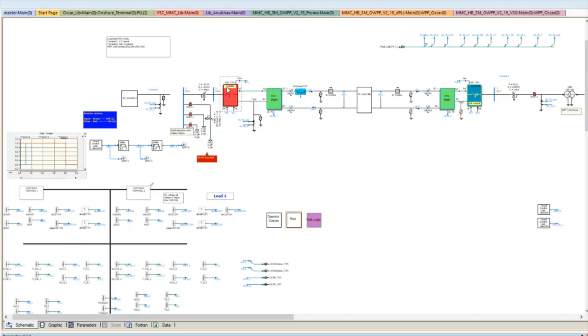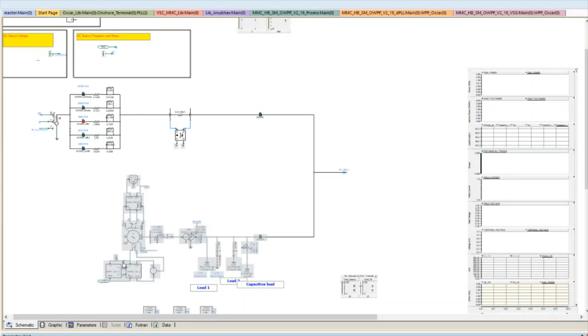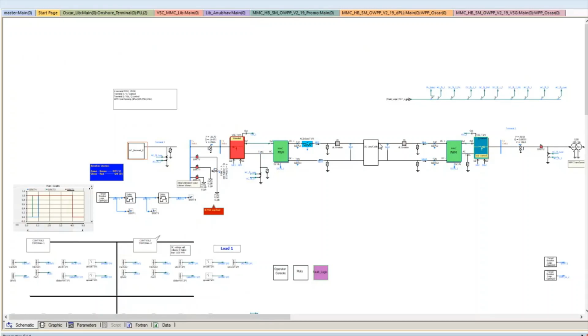For the onshore terminal, we have the AC network as a strong grid model, a Thevenin grid equivalent, which we do not use for the purpose of this study because it's a black start study that we perform. So energization of the wind power plant and the HVDC link, and the onshore side operates in an islanded mode. Instead we have a block load of about 30 megawatts, and the onshore MMC operates in islanded operation, which is opposite to what it would do in normal operation.